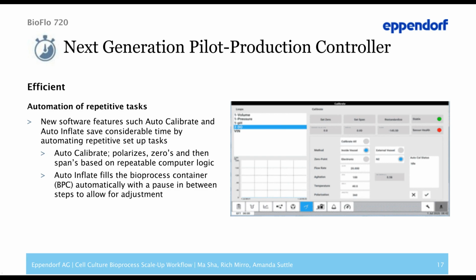users would select whether they want to calibrate a single or all DO sensors. They would select whether or not the calibration will be done inside or outside of a vessel, select the 0-point strategy, electronic or nitrogen, and then select key variables like gas flow rate, agitation, and temperature, as well as polarization time. Simply press play, and the system automates the process, which can save up to 8 hours if you're looking at an analog DO sensor, which requires 6 to 8 hours of polarization. So not only does it save time, but it also creates a repeatable DO calibration.